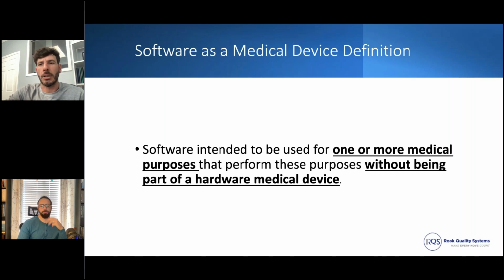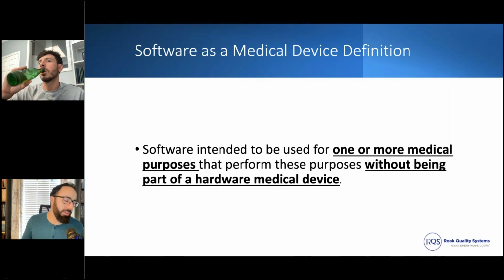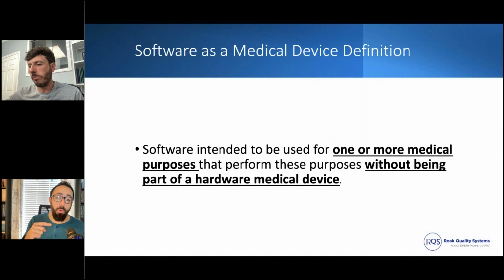Dwayne, any other thoughts on hardware testing before we go into some more software documentation? No, that was it. Just from the biocompatibility side, it's just the things we've seen. And the only other one outside of that was even before biocompatibility, which is preclinical animal testing. Doing a non-GLP study before you dive into a GLP study and do some large animal testing. But that's all before that. So nope. Got it. All right.